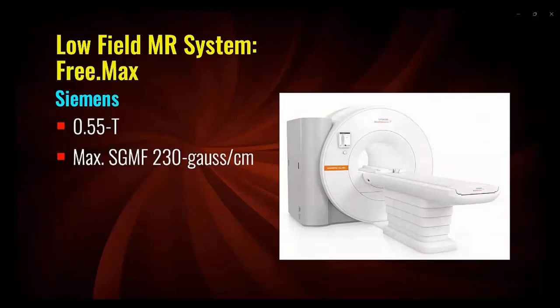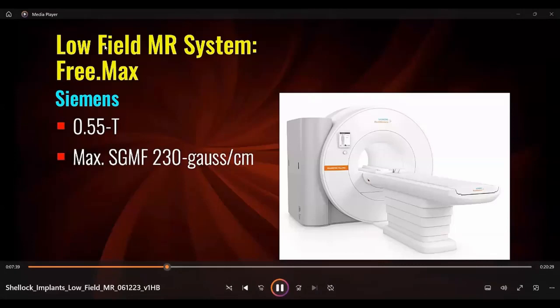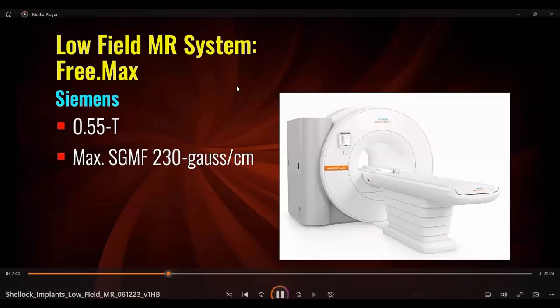This is the Freemax MR system from Siemens. It uses a horizontal field magnet that operates at 0.55 Tesla, and has a highest spatial gradient magnetic field of 230 Gauss per centimeter. The Freemax scanner is the first MR system with an 80 centimeter wide bore, which permits it to accommodate physically large patients.